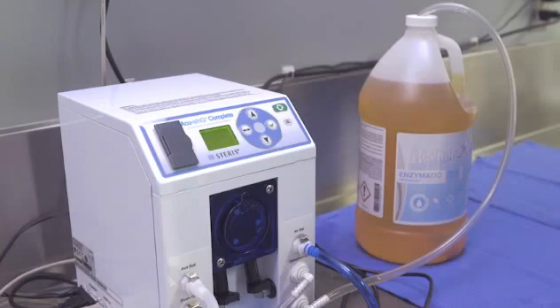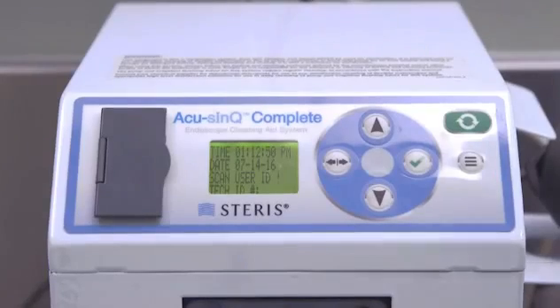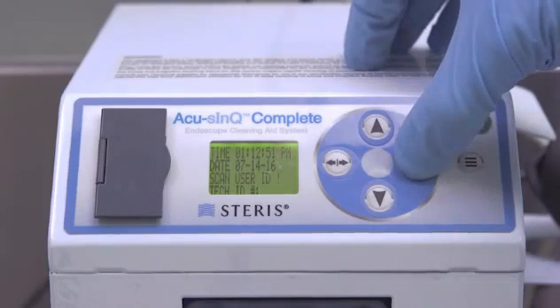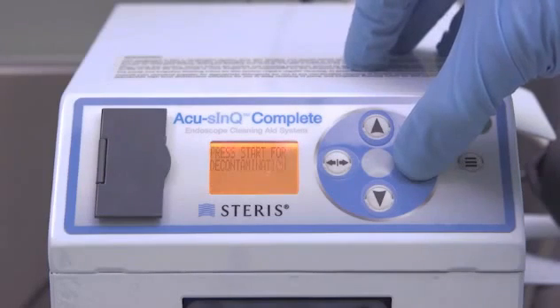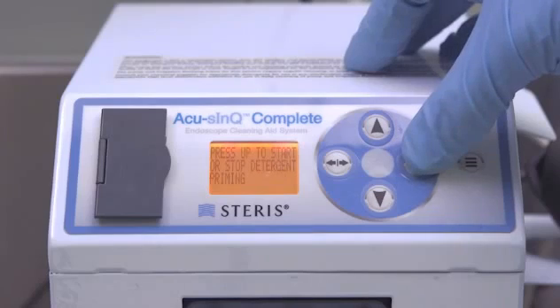To prime the unit, you need to first enter programming mode. To do this, please press and hold the Enter button until the screen changes from green to amber. Press the Enter button until you see a screen that says Press Up to start or stop detergent priming. Press the Up button to begin priming.